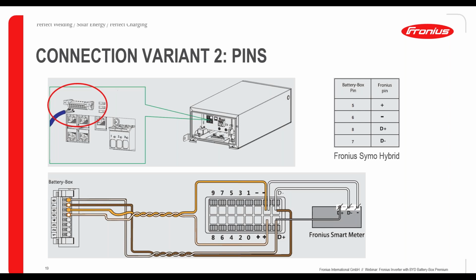Again, please make sure that D+ and D- are twisted to each other and that the cables are shielded. Nevertheless, we are recommending a Cat5 cable at least. And again, the plus and minus cables should also be twisted. Furthermore, you are doing the connection to the Fronius smart meter with D+, D- and ground. Again, please make sure that D+ and D- to the Fronius smart meter are also twisted so that there are no interferences on this communication path.